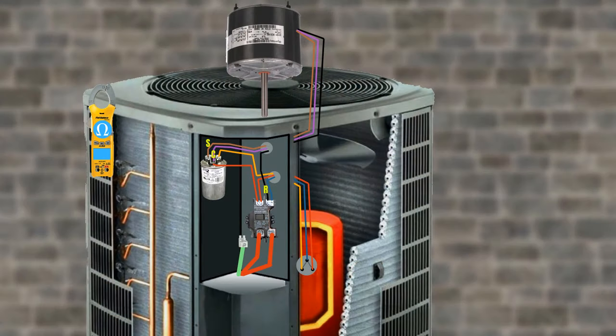I would say check the fan motor for a short to ground right now, but the main breaker or service disconnect fuses would have usually tripped by now. So let's check the motor windings first to see if we have an open or damaged winding.